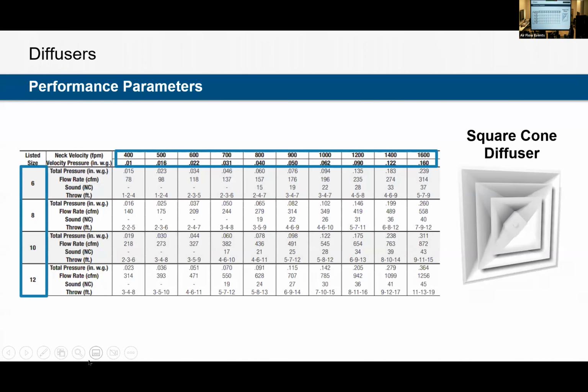Diffusers. When we're looking at cataloged diffuser performance, we're seeing some of the same numbers, and we see sound, we see our throw dimensions. Diffusers are gonna have a couple more variables in there. Your neck size can be variable. So even though you'll always have maybe a 2x2 diffuser, your neck size could change from 6 inch all the way up to 12 inch. And then catalog performance for different neck velocities. Usually, again, we're staying below 2,000 feet per minute. But we can see what all the different neck velocities are and the corresponding sound and throw. Sizing for sound and throw is usually more important than sizing for a specific neck velocity.